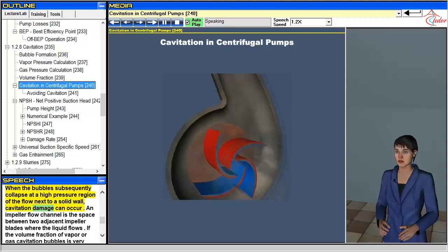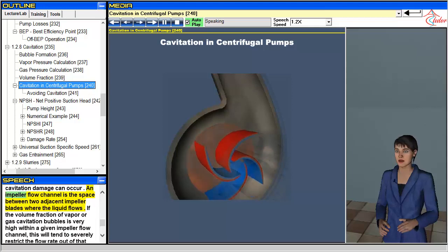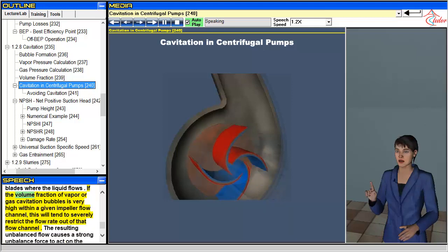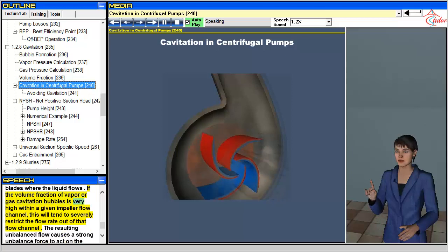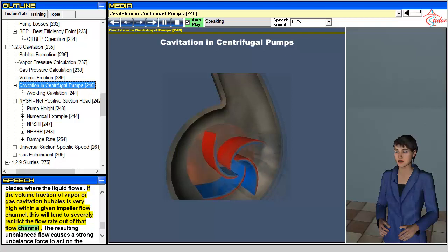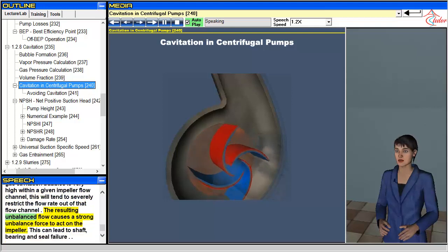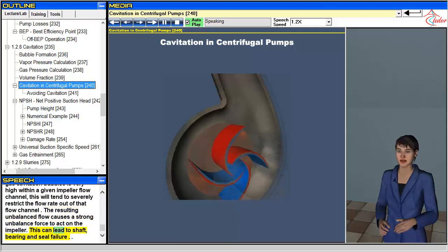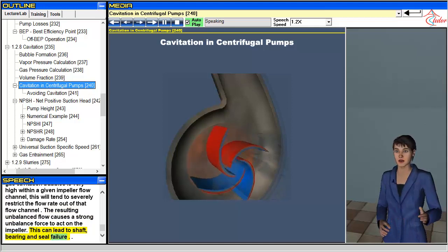An impeller flow channel is the space between two adjacent impeller blades where the liquid flows. If the volume fraction of vapor or gas cavitation bubbles is very high within a given impeller flow channel, this will tend to severely restrict the flow rate out of that channel. The resulting unbalanced flow causes a strong unbalance force to act on the impeller, which can lead to shaft, bearing, and seal failure.